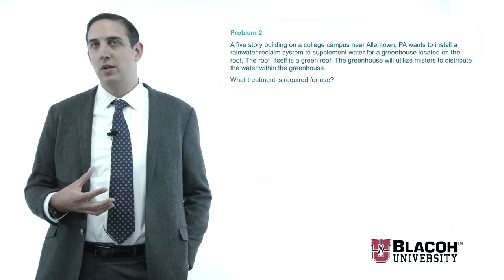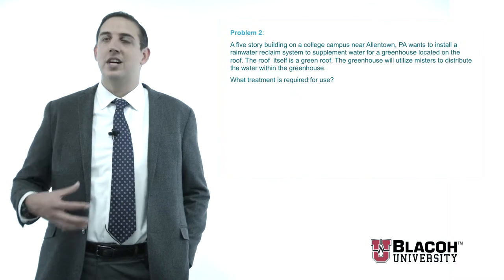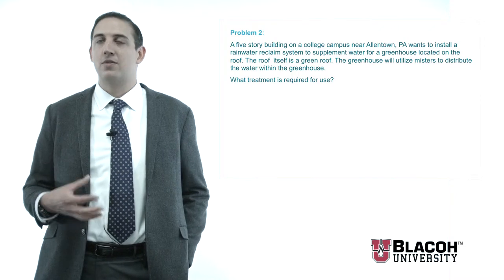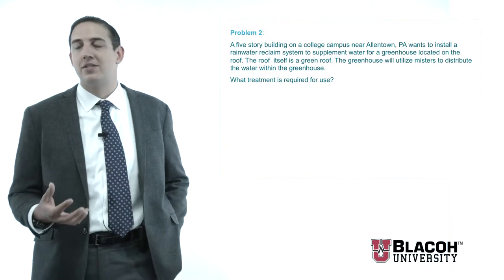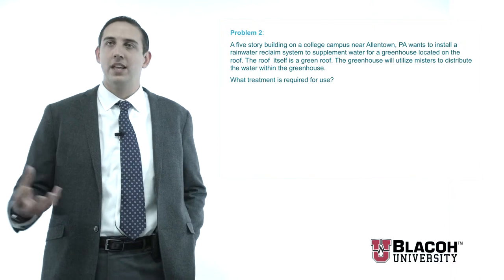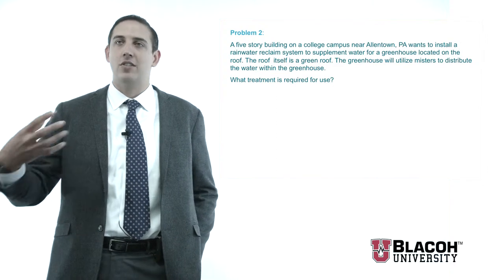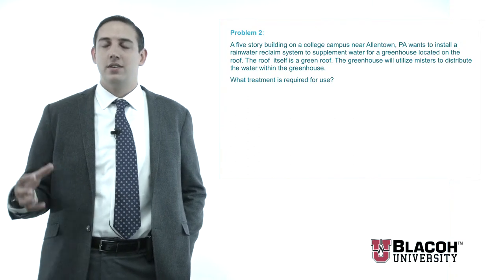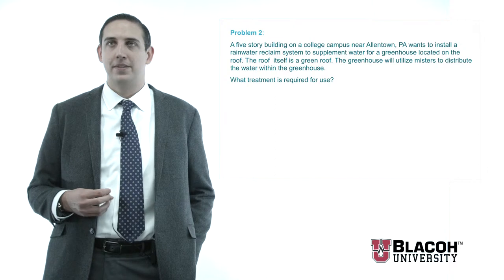We know the composition of our roof is a green roof. A green roof — for those who don't know — is essentially a roof that has plants planted on it and acts like an irrigated area. Green roofs in general are not ideal for reclaimed water systems for two reasons: one, the green roof itself eliminates a lot of the water that could be captured, as it's used for irrigating the plants on the roof, so your roof catchment surface is decreased. Two, you're introducing essentially ground-level contaminants onto your roof, so you'll see a much higher level of particulate matter.